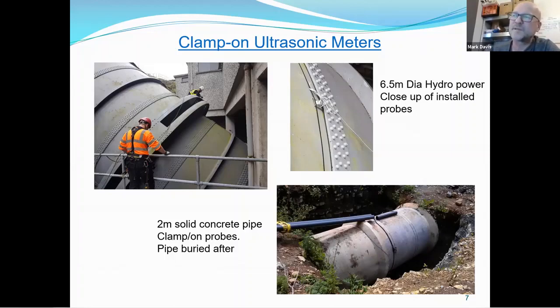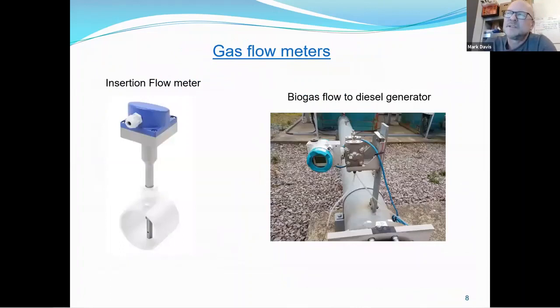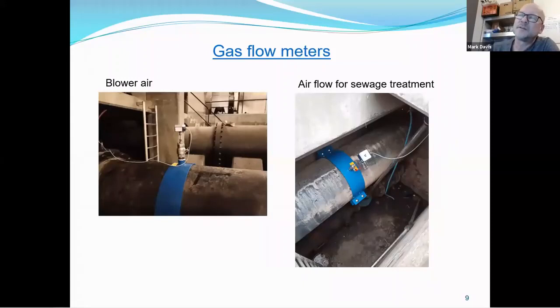Gas flow meters, relevant for water treatment. If you have biogas generation, which you use for generating power, you will want to measure that, and you can use different types of flow meters for that. The one on the right is an example of biogas going to a containerized diesel generator. It's quite a common application. This flow is slow, and it's also what we call dirty. It's corrosive, it may be wet as well. But cleaner airflow examples, this is blower air going to aeration basins for raw sewage treatment. Again, small insertion meters, these are installed without the flows being shut down.